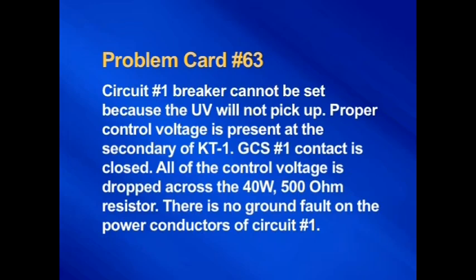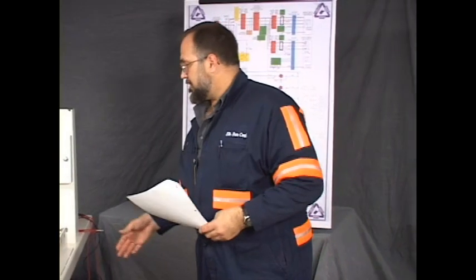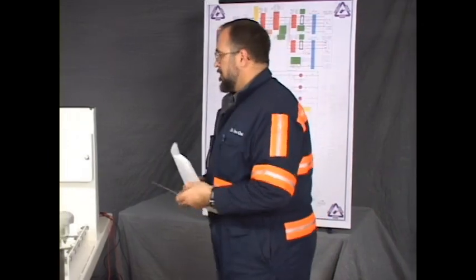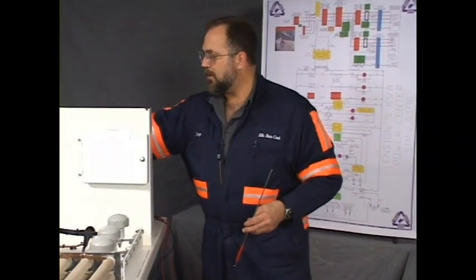Problem card number 63. If the apprentice at the test center should draw this problem, circuit number 1 breaker cannot be set because the UV will not pick up. Proper control voltage is present at the secondary of KT1. GCS number 1 contact is closed. All of the control voltage is dropped across the 40 watt 500 ohm resistor. There's no ground fault on the power conductors of circuit number 1. Does that sound familiar? It should, because it's word for word the same problem as problem number 54 that we talked about earlier.